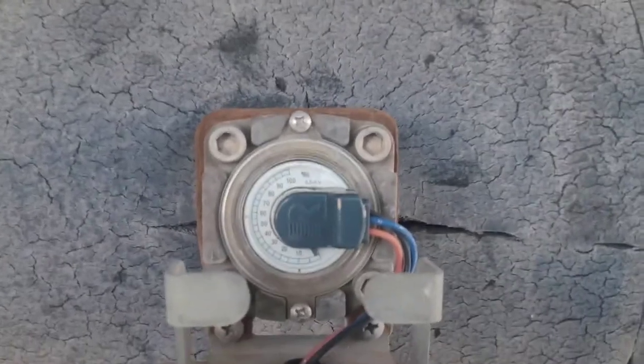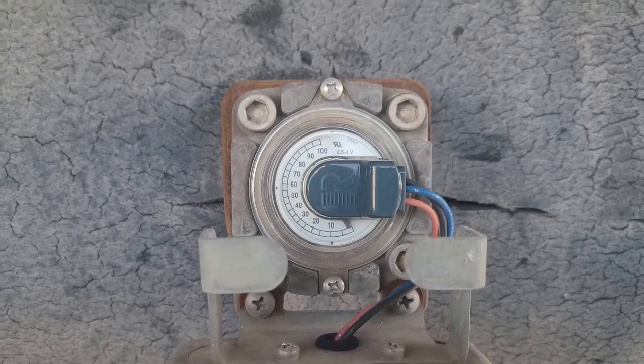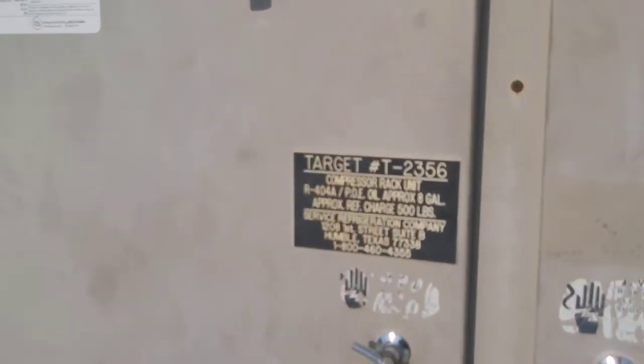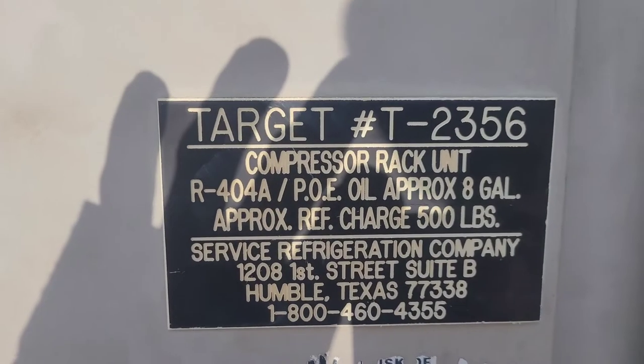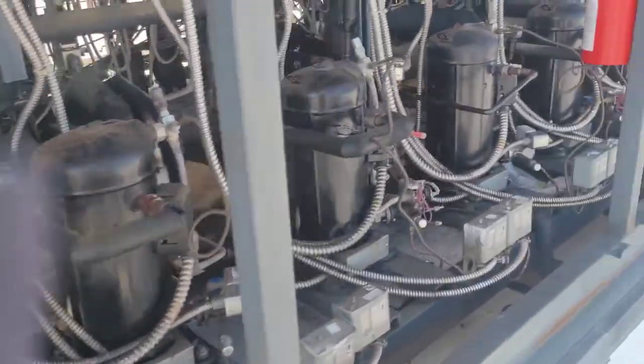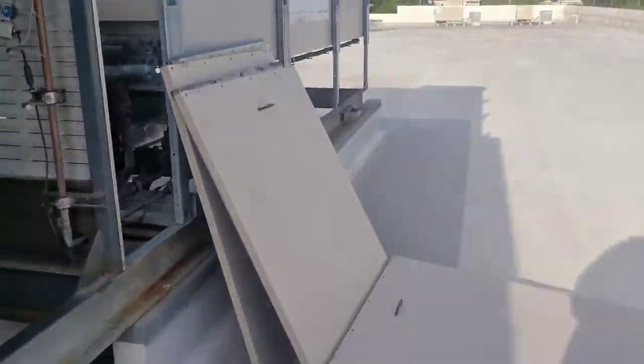So this one I'm working on here, this is the liquid level receiver line liquid level indicator. Do you see, I told you. Yeah, see all the compressors there? This unit takes 500 pounds. So 500 pounds at 0%.